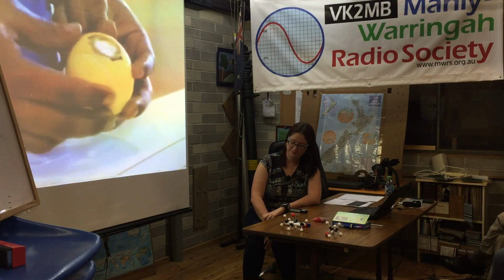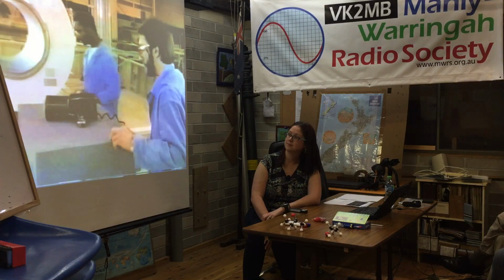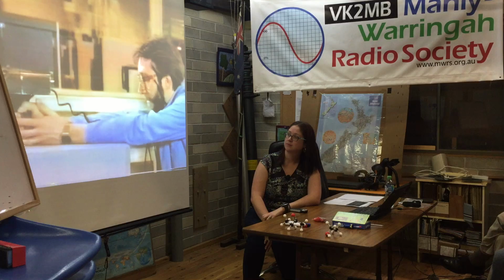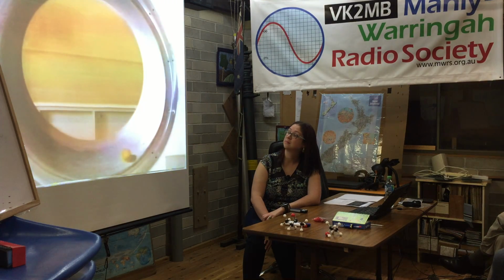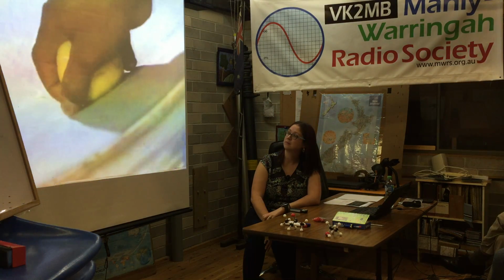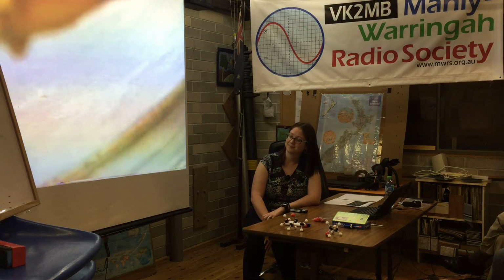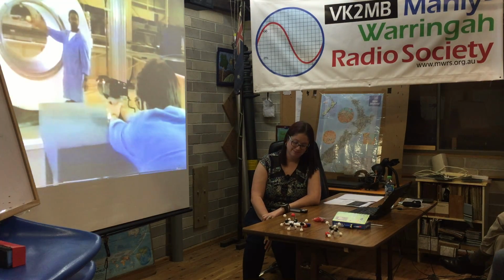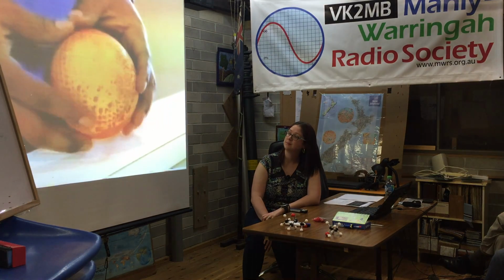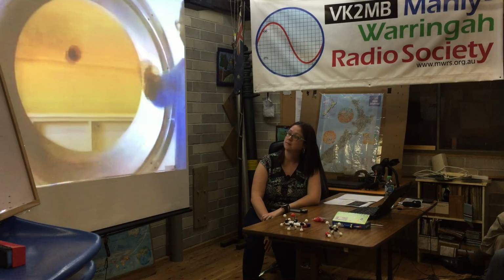For this experiment, we'll take a rubber ball filled with steel shot and toss it into the magnet. A radar gun will indicate the speed. In these tests, we measured speeds of 20 miles per hour or more. But more important is the rapid acceleration and unpredictable direction. The ball can take any number of routes as it flies into the magnet bore. Imagine the damage that could happen if this were a wrench, oxygen bottle, or other sharp or heavy object bouncing around like this.